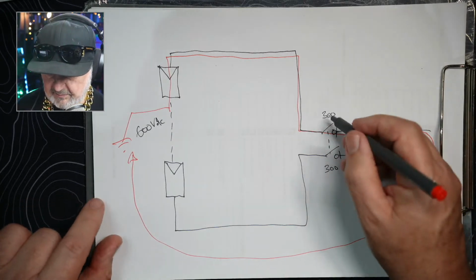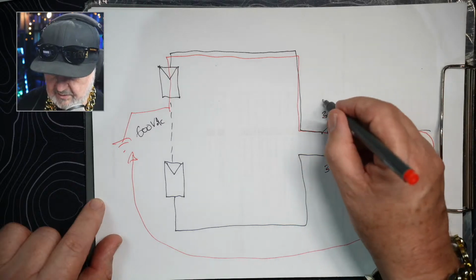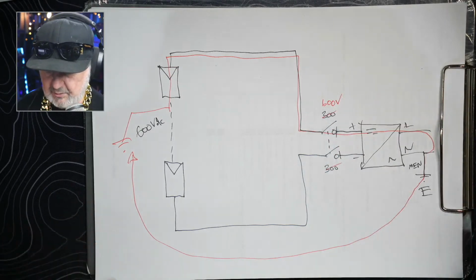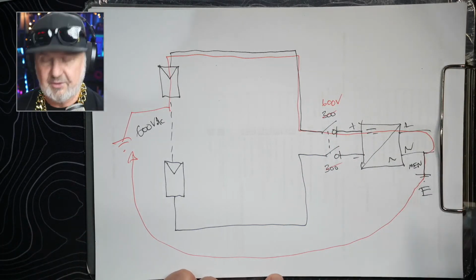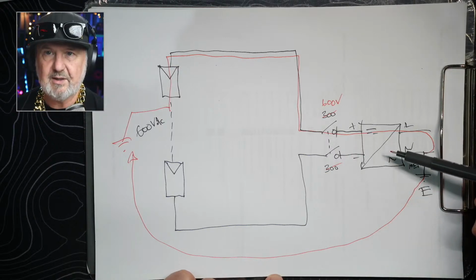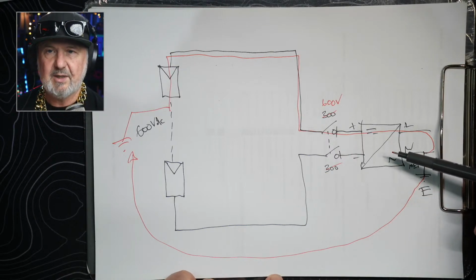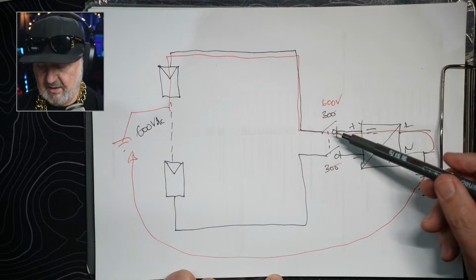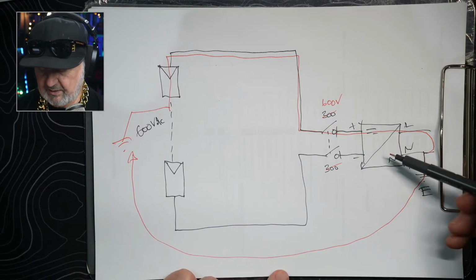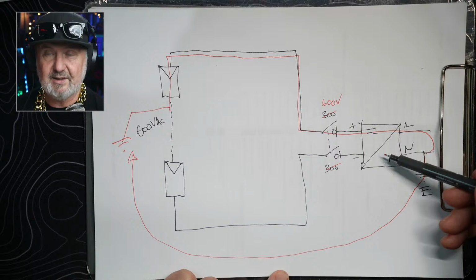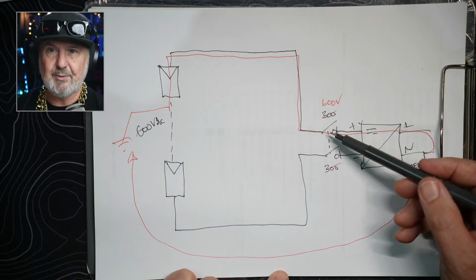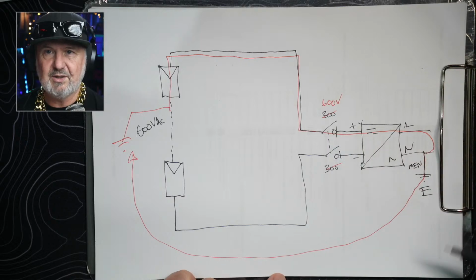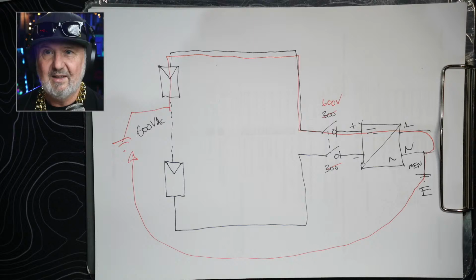You'll notice now that that's not true. It's actually 600 volts across one switched pole. And so moving from galvanically isolated to non-galvanically isolated, technically called non-separated, effectively doubles the voltage under fault conditions across the switchgear. And so therefore the rating goes up a lot.